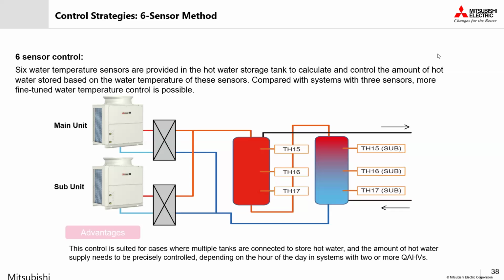So our system efficiency, or our COP, can drastically improve with those warmer ambient temperatures. So with things like the 6 sensor method, we can leverage those to adjust our start and stop points throughout the system. For example, in the summer, we can allow more of the storage to be depleted before giving the heat pump the on signal, which means longer run times at lower frequencies and less short cycling when we have that additional capacity. Now, in the wintertime, we can set the system to recharge sooner after less hot water is being drawn down, making sure that there's plenty of time to recover the storage between those peak usage periods. This type of control not only improves efficiency, but it reduces the on-off cycling of our compressors. So it helps us get the most out of the heat pump's operating range.